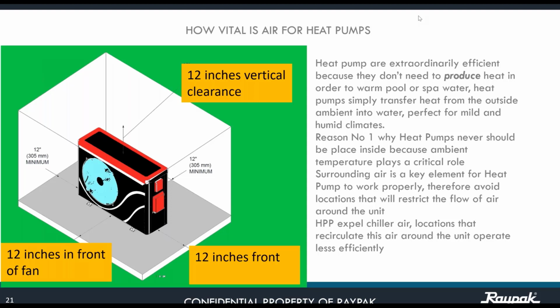They transfer heat from the outside ambient into the water, the reason why they are so perfect for mild and humid climates. Surrounding air is a key element for the heat pump to work properly. Therefore, avoid locations that will restrict the flow of air around the unit. Remember, they expel chill air, okay?